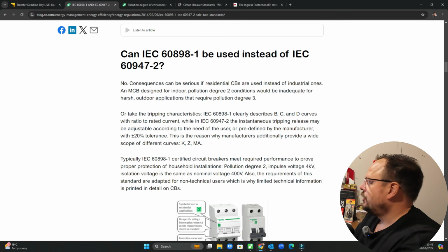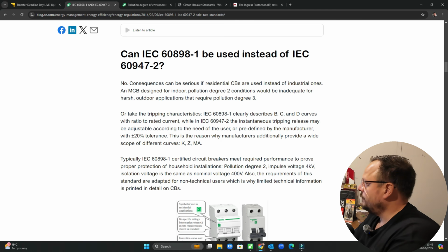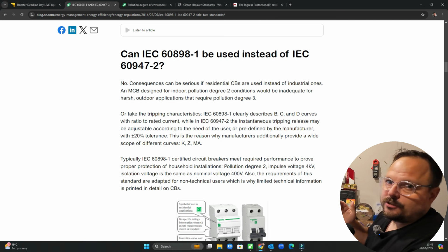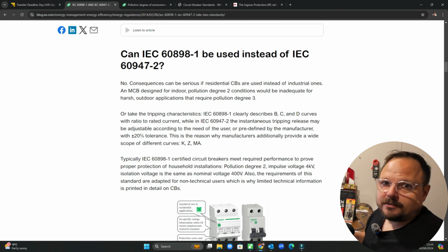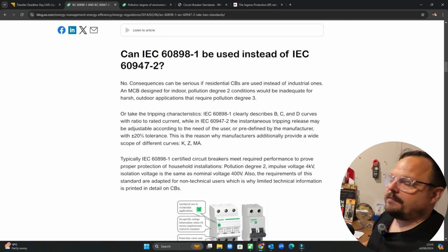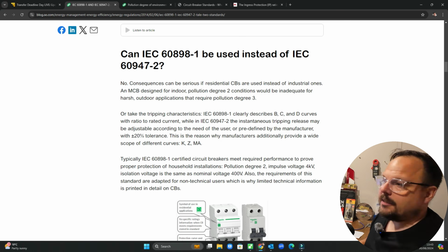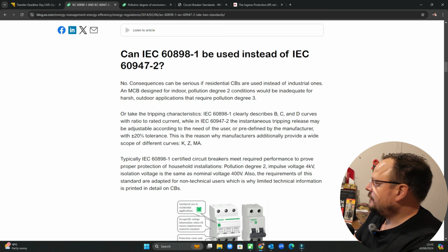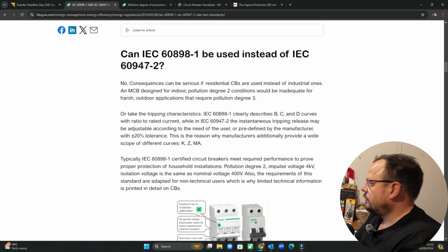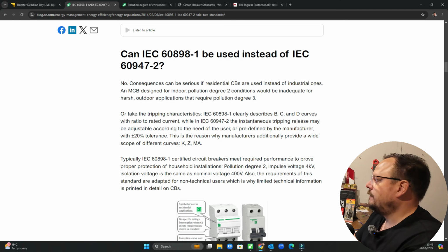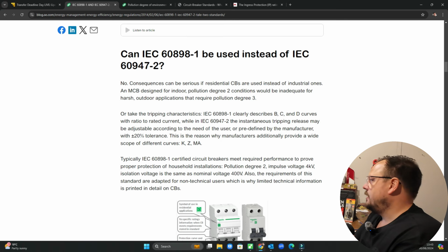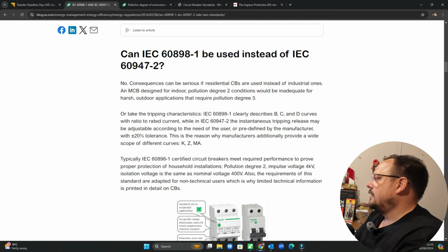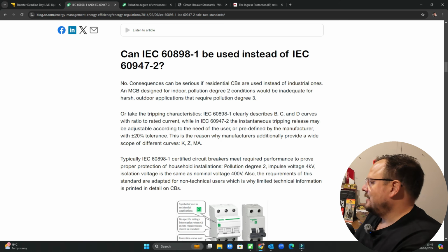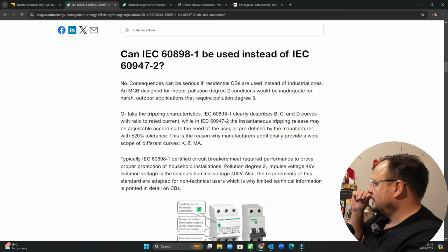So this is from Schneider Electric, and this is basically, can an IEC 60898-1 be used instead of a 60947-2? So your 60898s are your basic MCBs that we've just looked at earlier in the video, and your 60947-2s are those MCCBs. And it's saying here, no, the consequences can be serious if residential circuit breakers are used instead of industrial ones. An MCB designed for indoor pollution degree 2 conditions would be inadequate for harsh outdoor applications that require pollution degree 3. Or take the tripping characteristics, IEC 60898-1 clearly describes B, C and D curves.